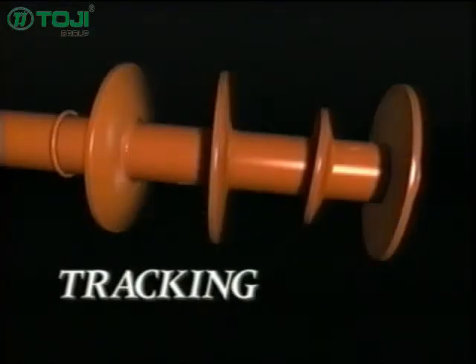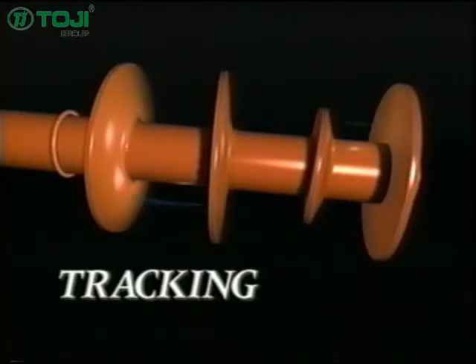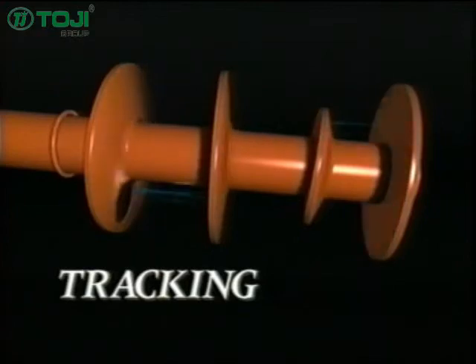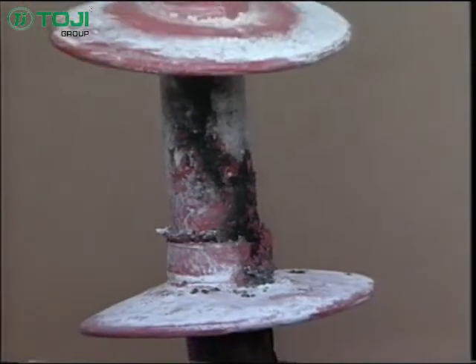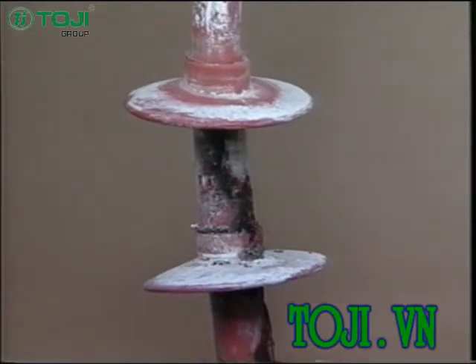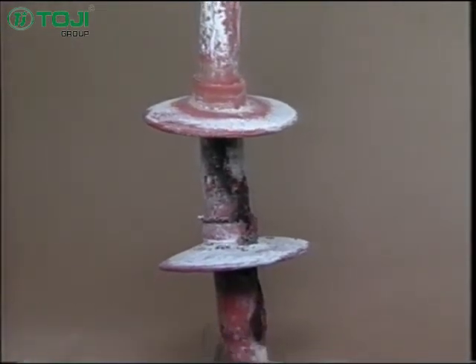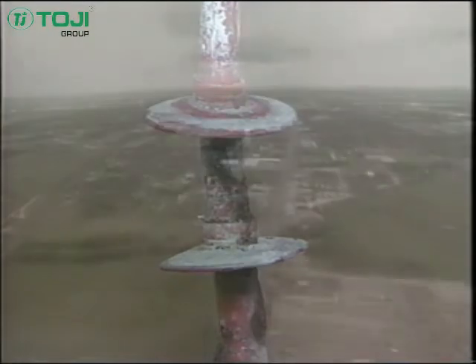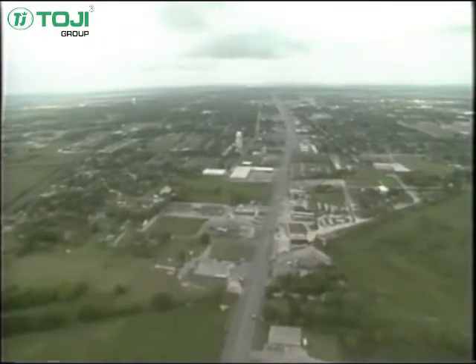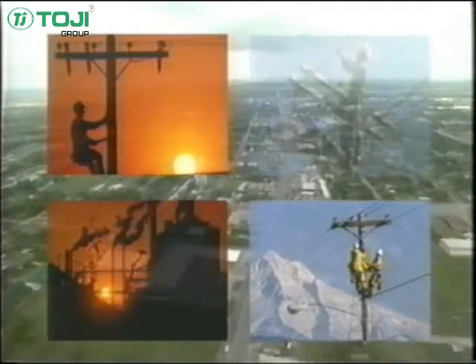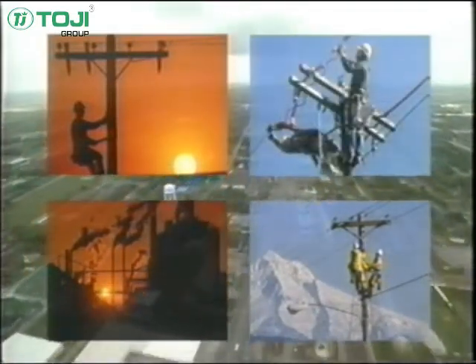Tracking is the actual decomposition of the insulation material caused by the passing of the electrical leakage current on the surface of that material. Organic materials such as EPR and heat shrink produce a carbon ash as they break down under constant electrical current. That carbon ash forms a conducting path which reduces the surface resistance, causing further current leakage and erosion, which eventually leads to termination failure. This can be a difficult problem because tracking performance is also dependent on where the termination product is located. Vast differences in climates have very different effects on the performance life of any termination.